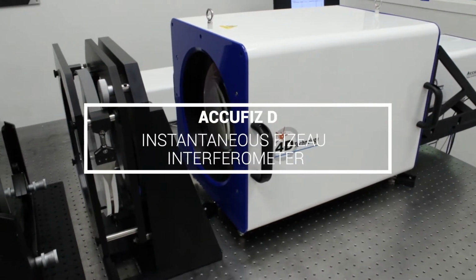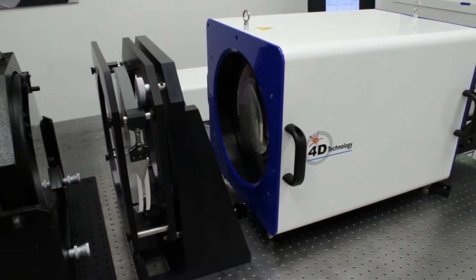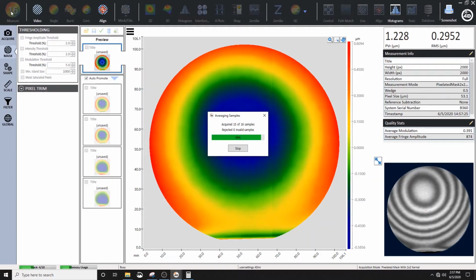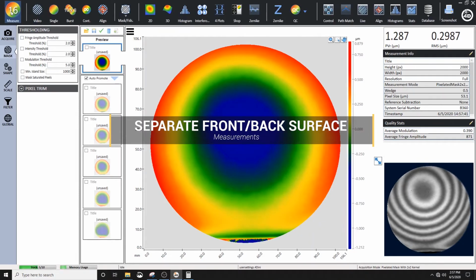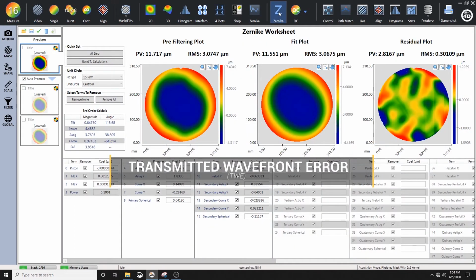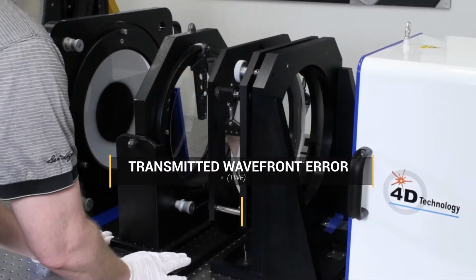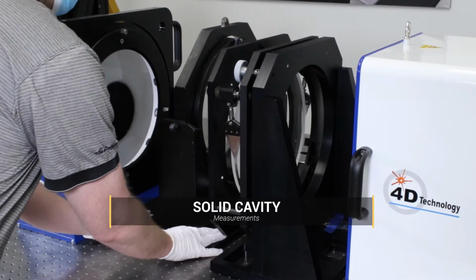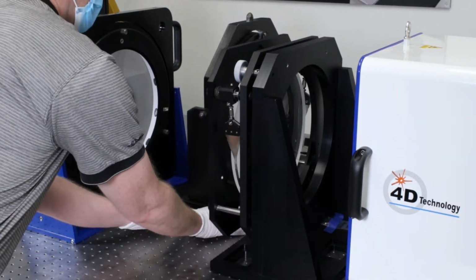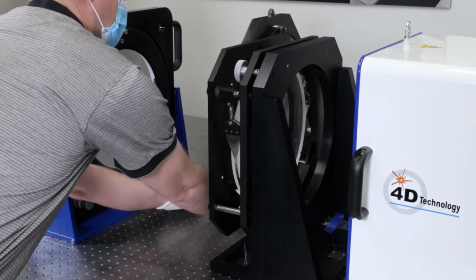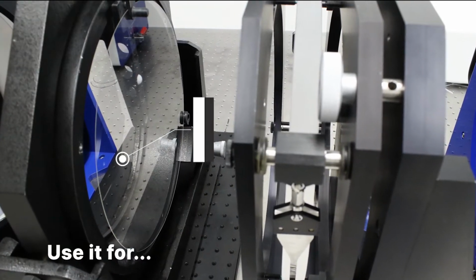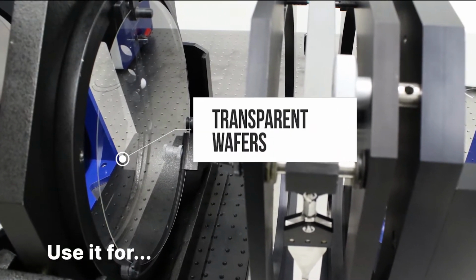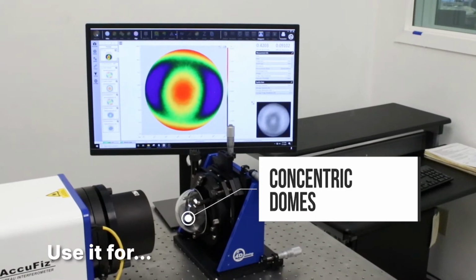The AccuFiz D is an on-axis instantaneous Fizeau interferometer from 4D Technology. It's the ideal solution for measuring surface shape, transmitted wavefront error, and solid cavity measurements of plane parallel optics and wafers. Achieve exceptional precision and measurement repeatability. Plane parallel optics, thin transparent glass or sapphire wafers, concentric domes.